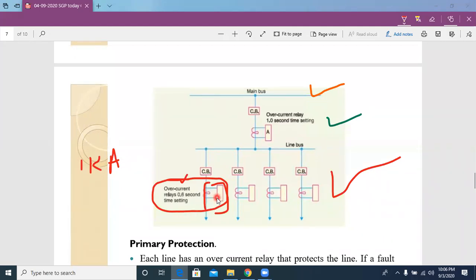As I already said, the relay continuously monitors the transmission line conditions. Here the condition is current. So the relay continuously monitors the transmission line current and compares it with its preset value, which here is 1 kiloampere. Now suppose the transmission line current value is 1.5 kiloamperes. This one is the fault.